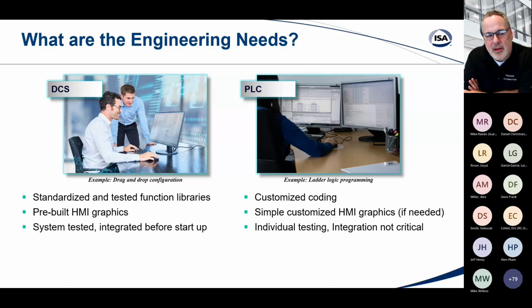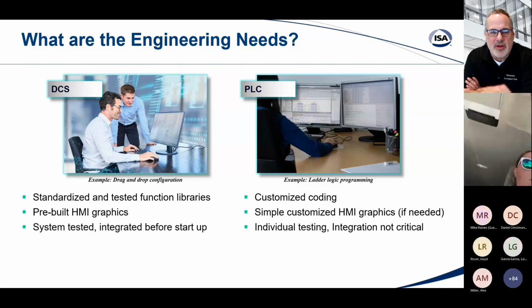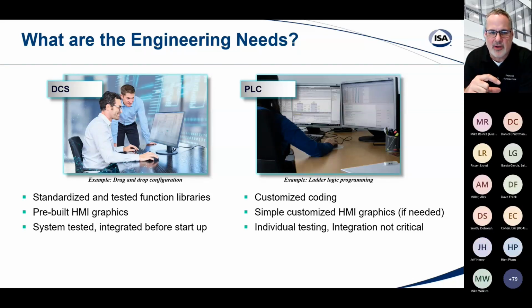The other thing is when you're putting your DCS code together, you also get, because of the common database we exploit, the ability to build these HMI graphics. So when you drop down a control valve operation in the DCS, some little block that is going to basically run that control valve, you also get an HMI element along with that. So your HMI screens are starting to be built with that intelligence. Now from the engineering side, you're dropping down that control valve or motor valve block or whatever. On the HMI side, you also get a little block icon that will come along with that, that's automatically tied to that function in the controller.